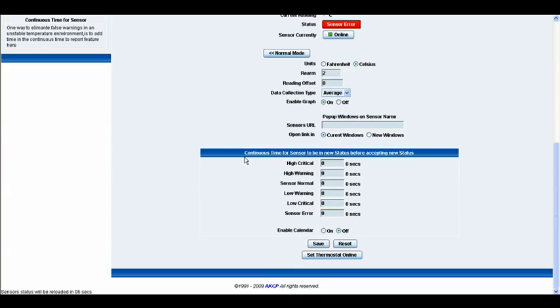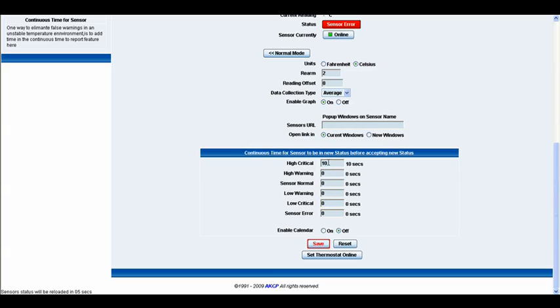Below that we have the continuous time for a sensor to be in new status before accepting the new status. So, when the sensor goes into a high critical status, you can type in 10 seconds here. Once it's been in a high critical status for 10 seconds, it will then display that status. And that's exactly the same for the high warning, normal, low warning, low critical and also for the sensor error.